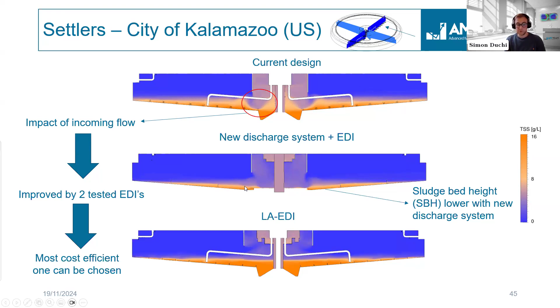So we tested different energy dissipation inlet systems to try to remove the energy and have a stable sludge bed. For example, at the bottom, you can clearly see that you have now a very stable sludge bed, no impact anymore from the inlet. And that's in the end what you want. And another case, for example, another discharge system where we were able to more efficiently remove the sludge. And in the end, that also lowered the sludge bed significantly.